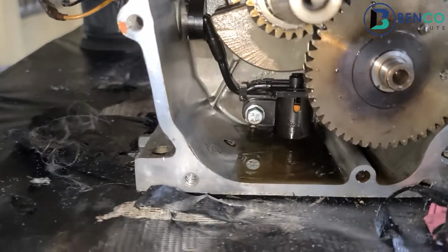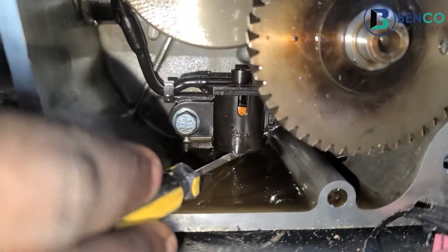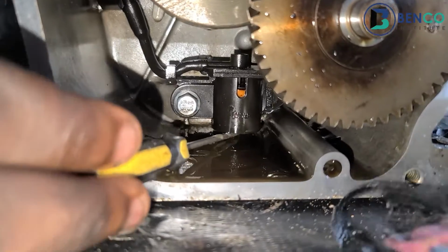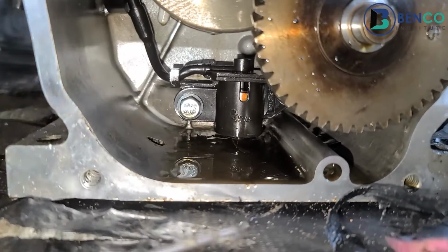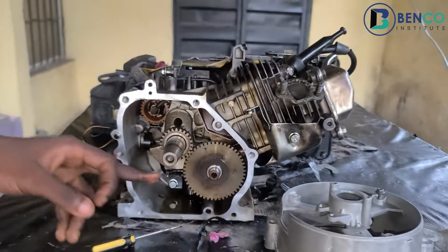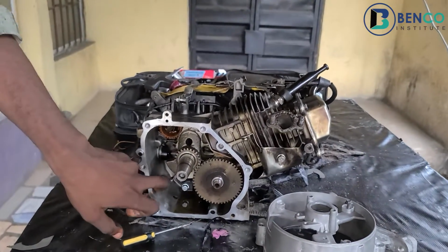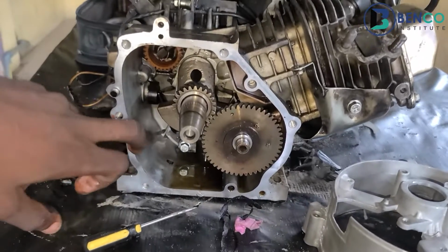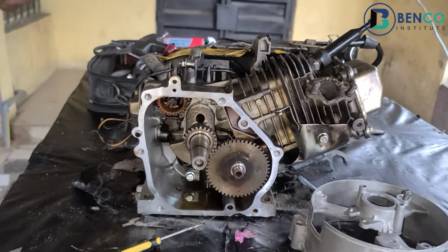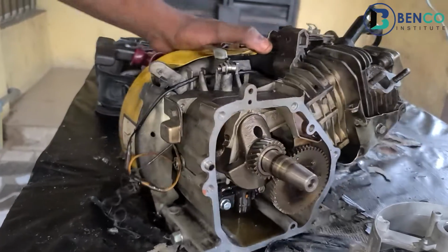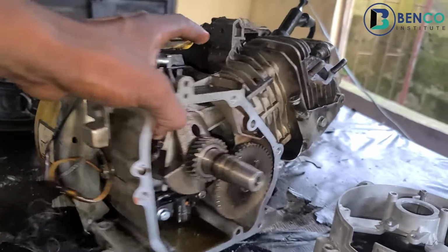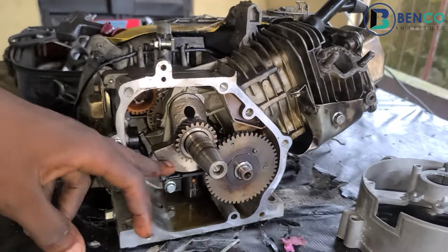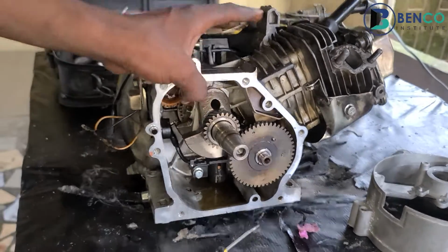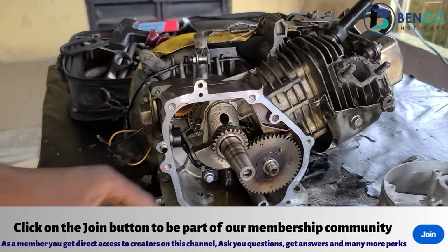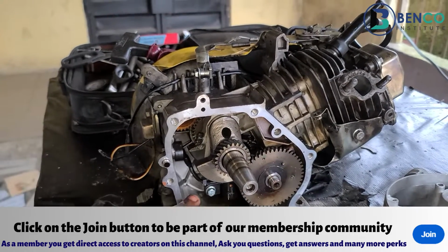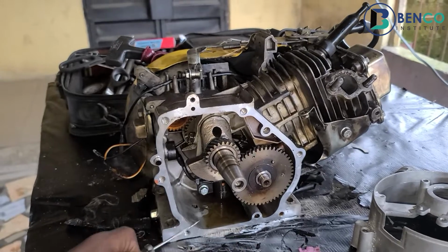Where there is no oil, there's a float pin here. If you see carefully, there's a pin here. I will take this out and explain better, but basically there's a pin there that touches the body of the engine. So that pin touches the engine and sends a signal to this oil sensor that says there is no oil in the generator. Actually, there's a particular threshold. It doesn't mean your generator has to be dry for this sensor to work, but for this generator, I think the threshold is around this region.